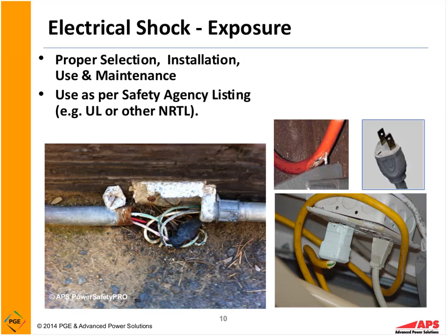On the lower left-hand corner here, this is from a bike path in eastern Oregon, where I rode up upon this, and you can see the junction box there is broken. So there is no equipment grounding path back, which we'll take a look at in just a minute. In other words, if the insulation on that wiring gets skinned, that whole section of raceway to the right, this J-box and the whole section of raceway, would actually become energized. And there is a pole light that would become energized right along a bike pathway where kids ride and where they play. The picture up to the right here, we see that there's a damaged cord.